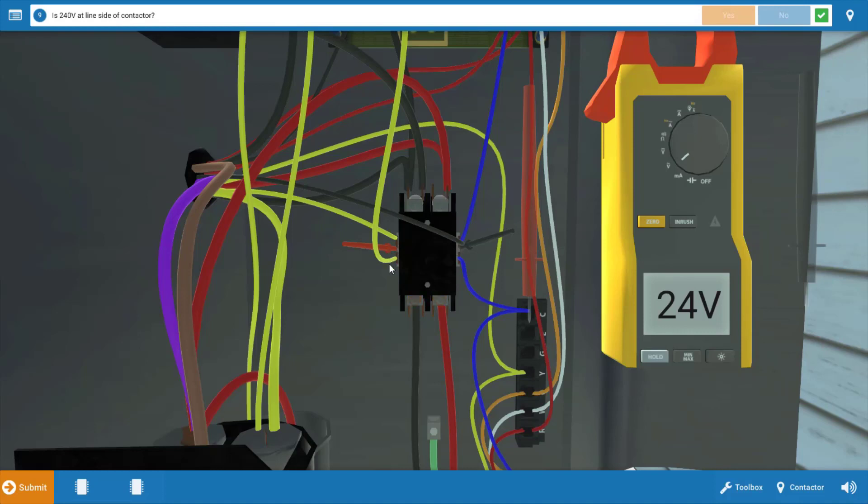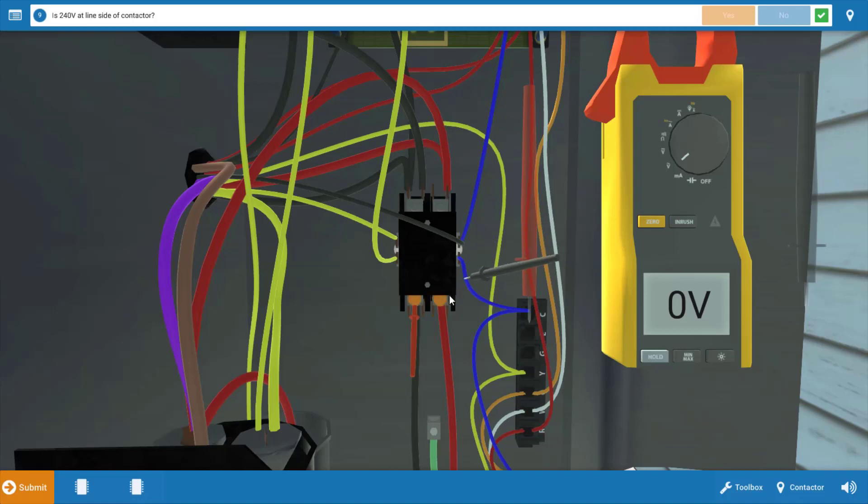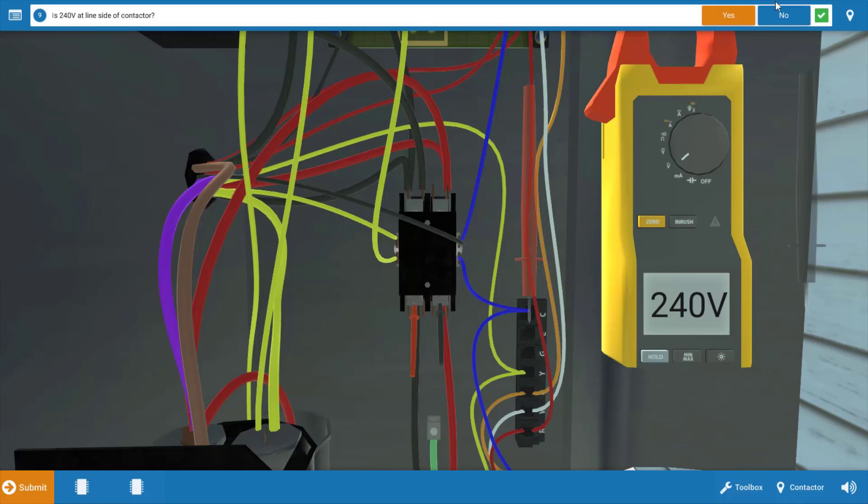Start by measuring line side voltage, and we should have 240 volts coming to the contactor from the disconnect. And we do have 240 volts, so the disconnect's not the problem. We've got power to the coil, and these contacts should be pulling in.